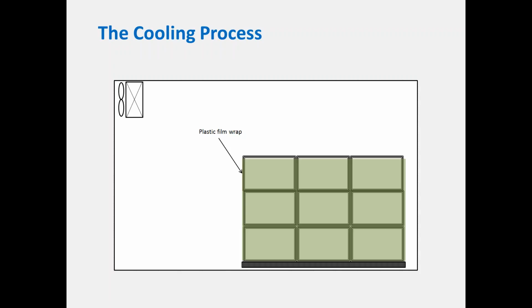Then, of course, you may wrap your product in plastic film. Probably not so much with horticultural products, because that would defeat the purpose of the air vents, but perhaps something like butter or cheese will have that extra film wrap. It's important to recognize that the wrap is another resistance that heat has to pass through. Finally, we need to represent the movement of air from the product surface, the external product surface—in this case the outside of the wrap—to the evaporator coil, if it happens to be up in one corner of the room.